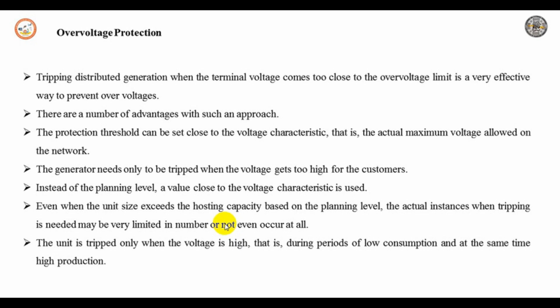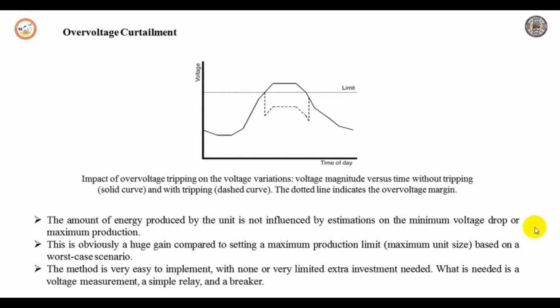Let us move on to over voltage curtailment. In over voltage curtailment, a scheme in which the production is reduced more when the voltage gets closer to the limit is a more efficient scheme. This will result in less loss of production than the over voltage protection, but some stability concerns remain.